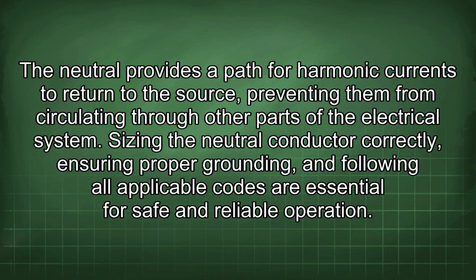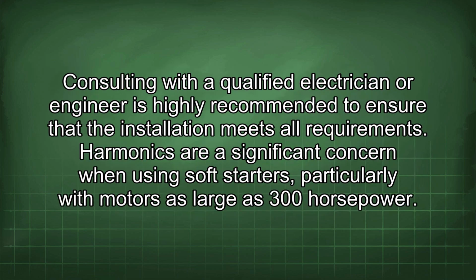The neutral provides a path for harmonic currents to return to the source, preventing them from circulating through other parts of the electrical system. Sizing the neutral conductor correctly, ensuring proper grounding, and following all applicable codes are essential for safe and reliable operation. Consulting with a qualified electrician or engineer is highly recommended to ensure that the installation meets all requirements. Harmonics are a significant concern when using soft starters, particularly with motors as large as 300 horsepower.